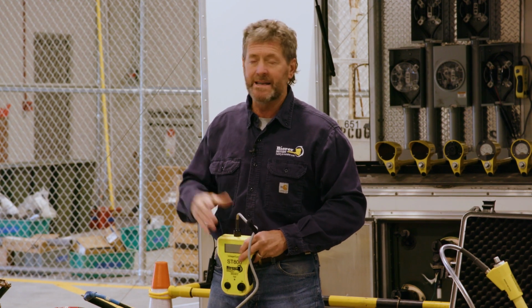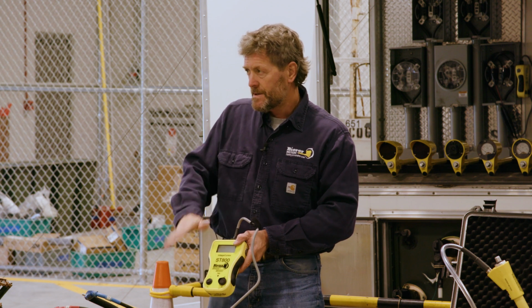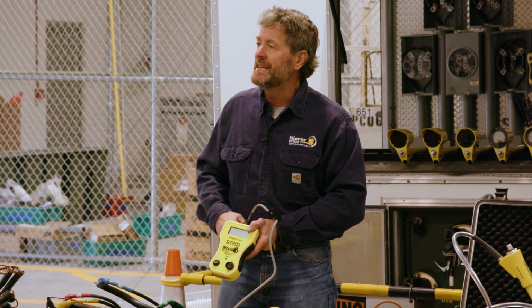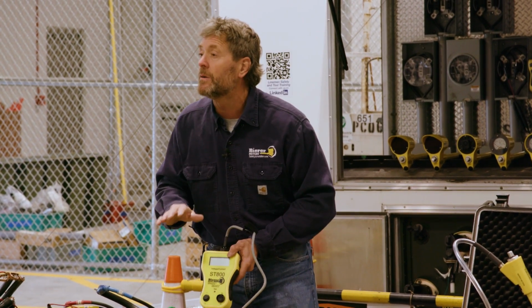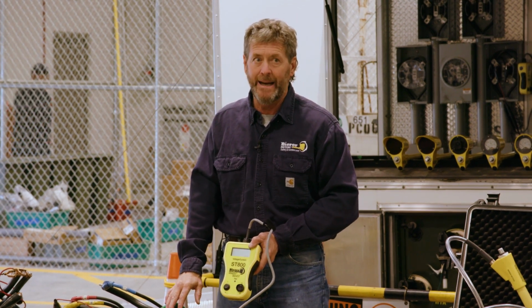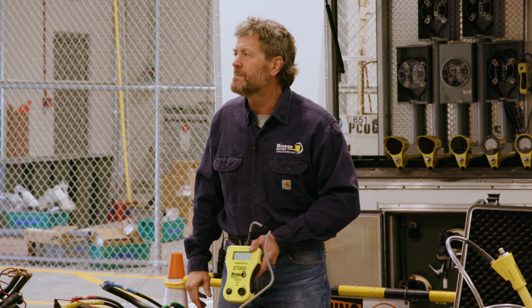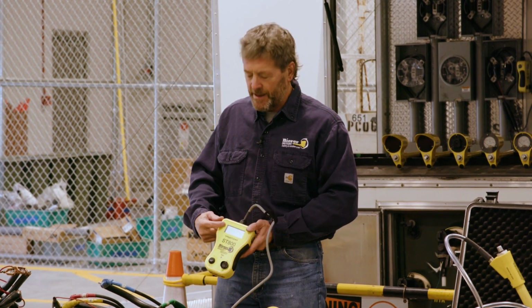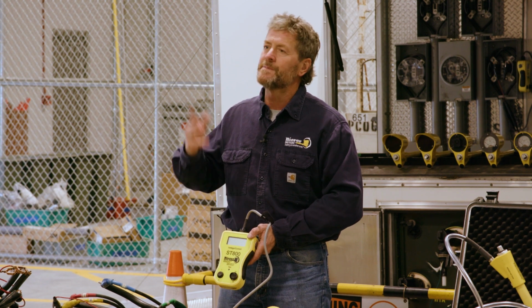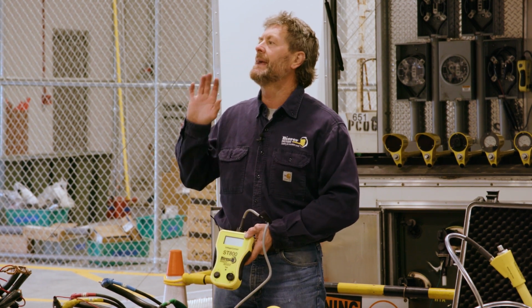So obviously one of those legs, hot leg 1 or neutral, are bad. And the tool's already telling you that. Then you're going to toggle from the voltage, toggle to the load, and it's going to sequence the count. You're going to see the count, and you're going to see the load climb up. But because you saw 100 volts, you know that the load climb up is going to be very slow because the integrity is bad. Sure enough, you're seeing a 2 amp jump each count. So it sequences the count on the screen to the load here. It gets up to 40 amps, falls on its face, and starts recounting. And you got a splice, or you got a lot of lift poles, and you hear a popping sound over yonder. So the tool's already, because it's in the clear, the tool's already found the issue for you.